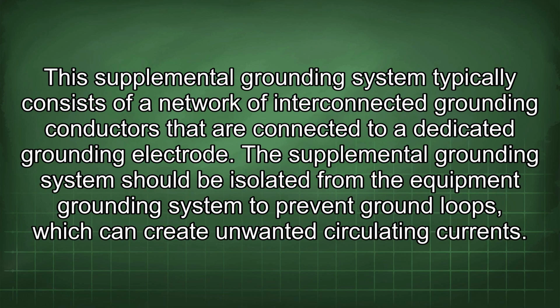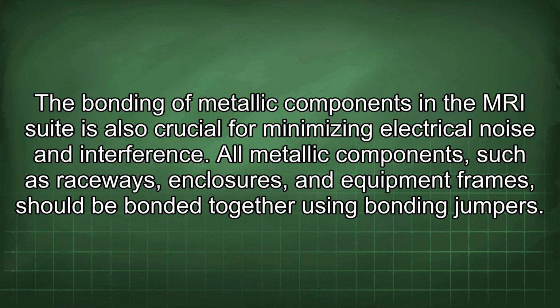This supplemental grounding system typically consists of a network of interconnected grounding conductors that are connected to a dedicated grounding electrode. The supplemental grounding system should be isolated from the equipment grounding system to prevent ground loops, which can create unwanted circulating currents. The bonding of metallic components in the MRI suite is also crucial for minimizing electrical noise and interference. All metallic components, such as raceways, enclosures, and equipment frames, should be bonded together using bonding jumpers.